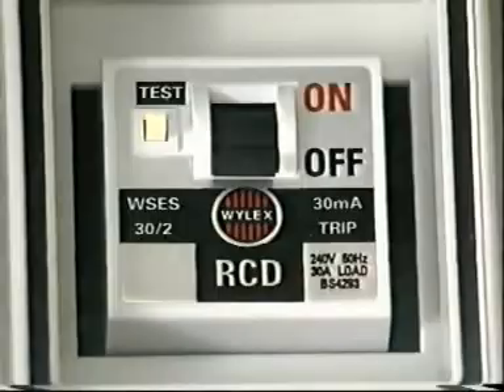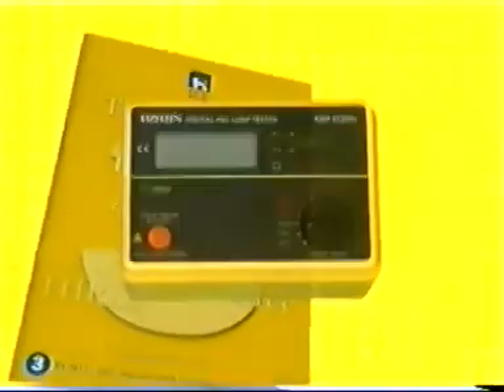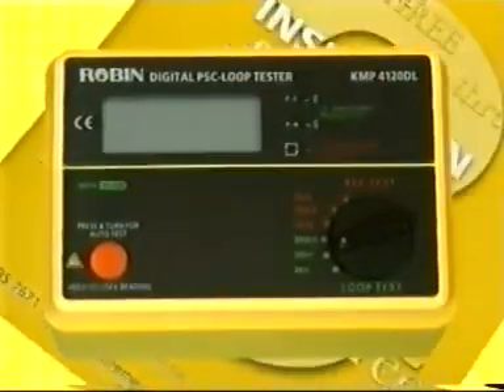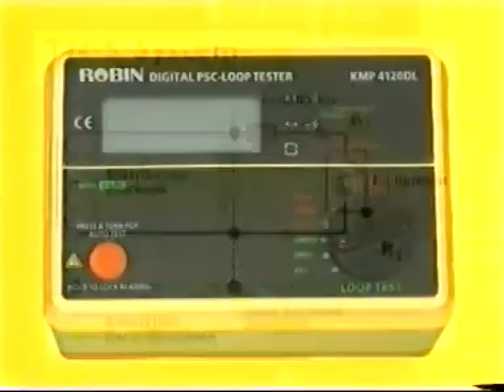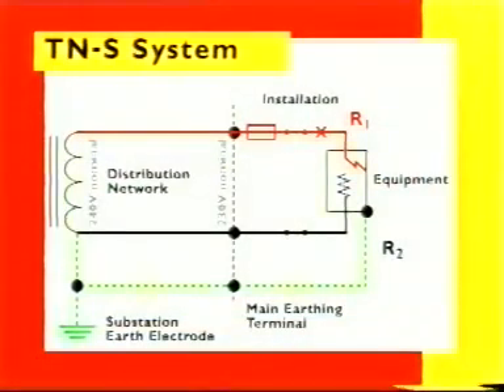Where an RCD is used for indirect contact shock protection, IEE Guidance Note 3 permits measurement of electrode resistance using a loop impedance tester. In the event of a phase fault to exposed conductive parts of consumer's equipment, sufficient current must flow to enable rapid operation of the circuit protective device. The earth fault loop impedance test will measure the impedance of the fault current loop path.